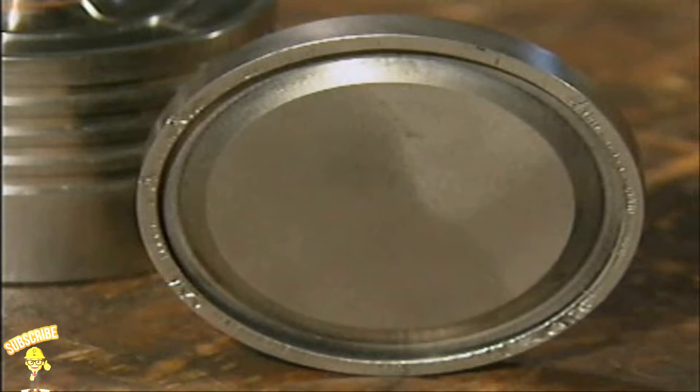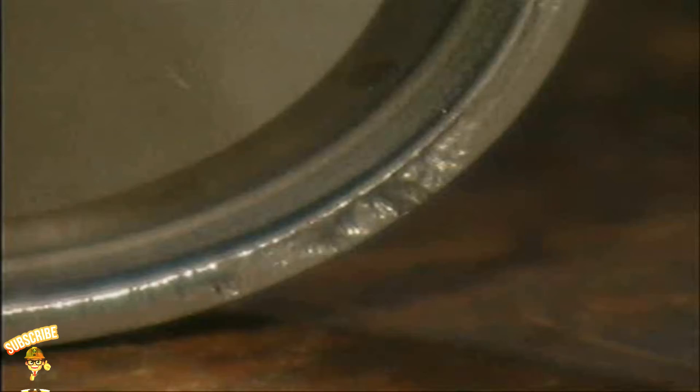Chattering can seriously damage both the disc and the seat because it promotes steam cutting. Steam cutting occurs when the velocity and the temperature of the escaping steam are so high that the steam cuts into the metal of the valve's disc or seat.